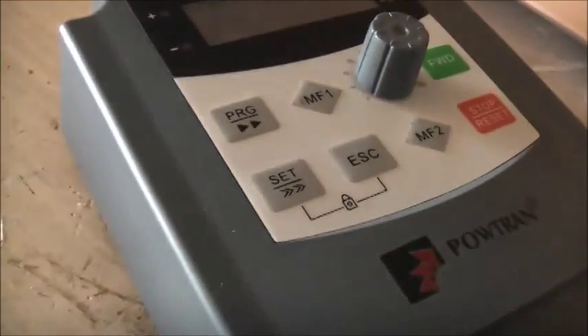Carefully lay that back. Interface board there — that's the interface pad module. And this is all the programming on this board here. This is all your PLC interface. There's a little relay there which will click to turn on the braking resistor if it has one connected.